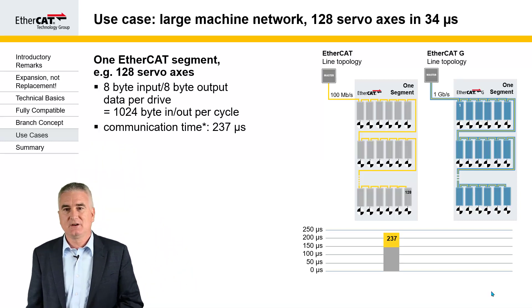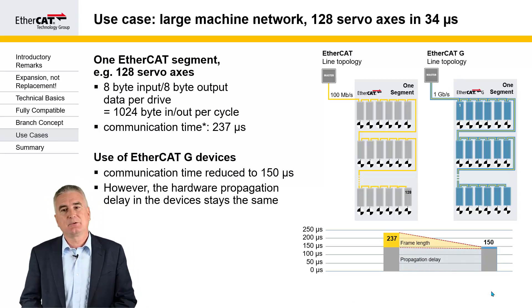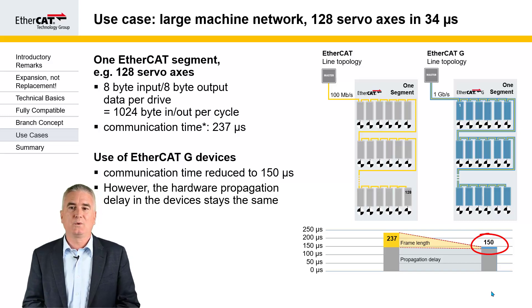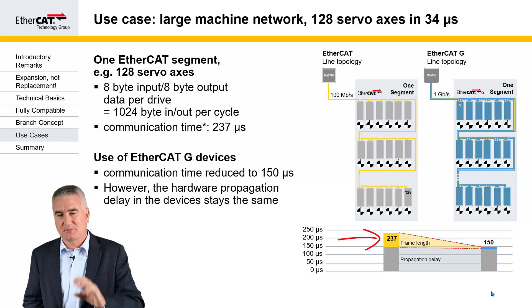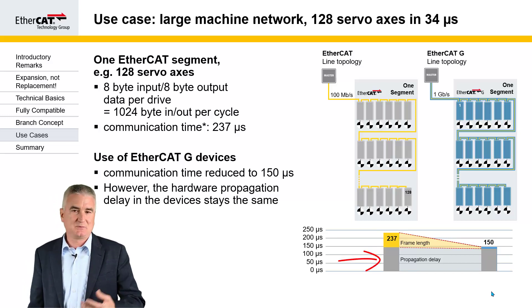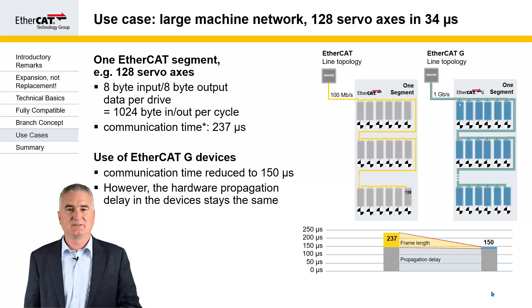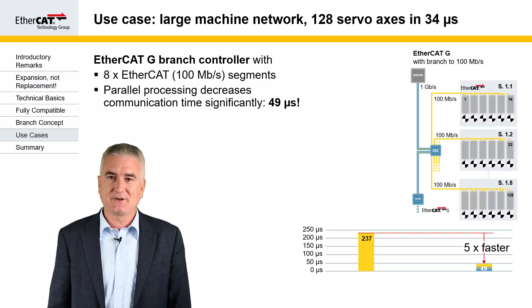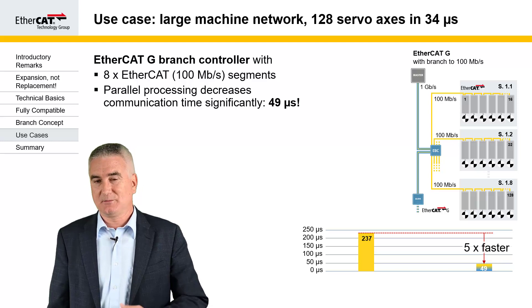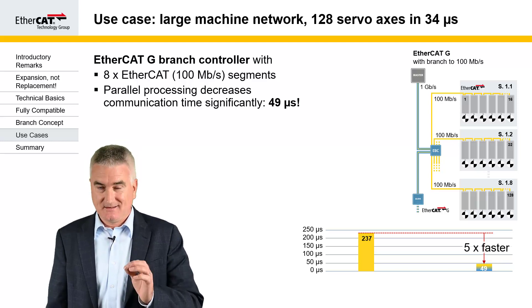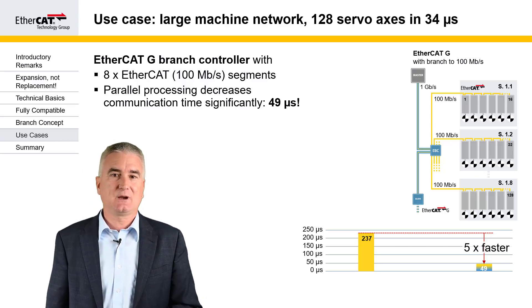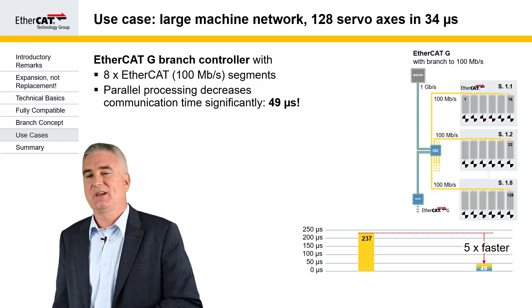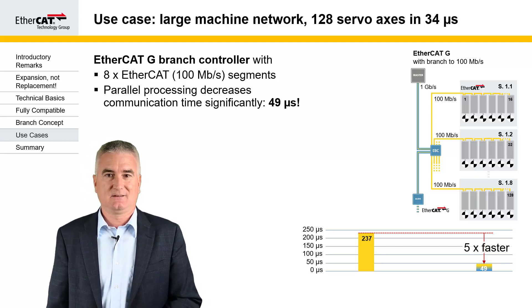If we go with gigabit throughout, we win, but only a little bit. The communication time is reduced to about 150 microseconds because the propagation delay remains pretty much the same — we only win on the frame length. The frame becomes shorter, but the propagation delay time remains similar to 100 megabit, so the gain with regards to communication time is not very convincing. However, if we introduce the branch controllers and split our network into 8 sub-segments, we win a lot. The communication time goes down by a factor of 5, and we still use the same 100 megabit drives as before. We just run the 8 segments in parallel and this gives us a lot of performance improvement.